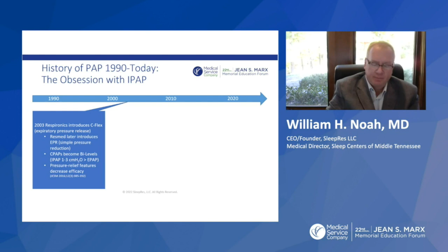2010, it gets worse. Philips introduces their mask resistance setting because the engineers were told you've got to maintain that pressure during inspiration. You got to maintain that IPAP. You can't let it drop like these old machines we had in the study with Dr. Stroh and Dr. Redline. You can't let that happen. Well, but we got these nasal pillow masks and they're going to drop pressure. Then you got to jack it up. You got to jack it up when they put that nasal pillow on.